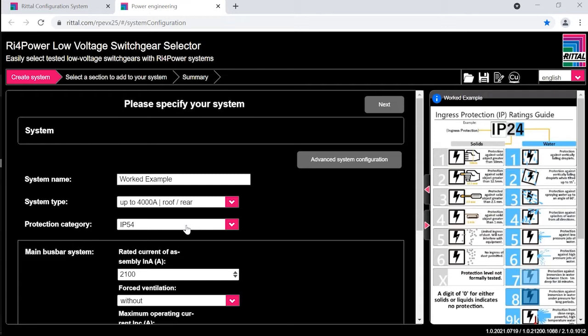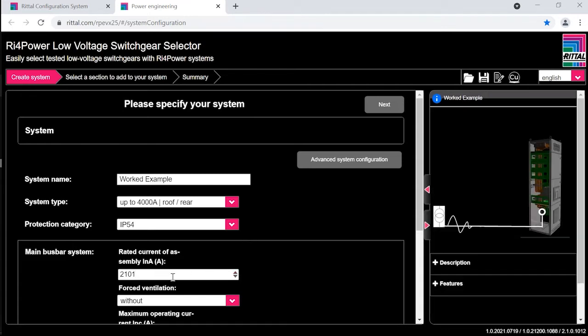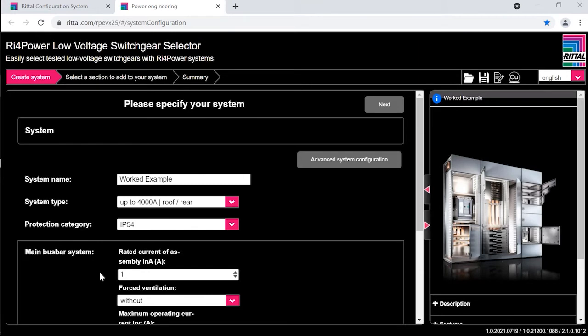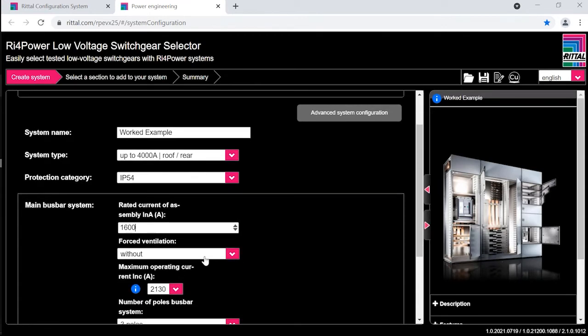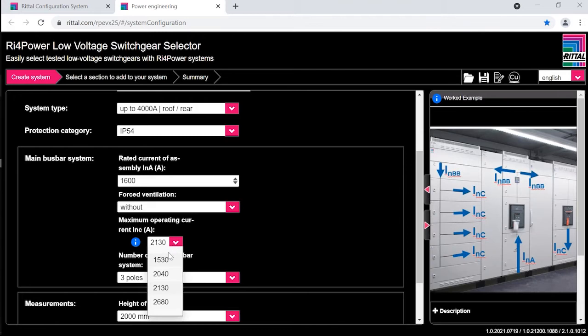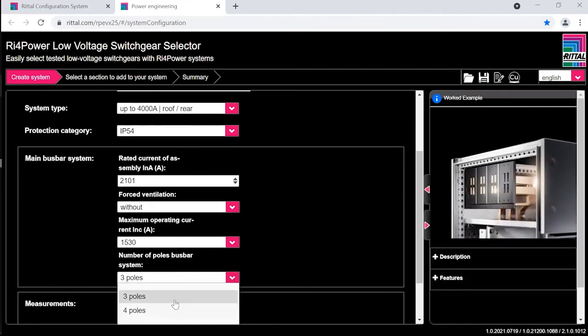We also need to reference our manual on the compartment sizes for the ACB and MCCB circuit breakers. With that in mind, we'll select the rating as 1600 amps for the bus bars. The load current is 1200 amps, which is the design current, but we'll fit in a figure of 1600 amps, a little bit of tolerance there. We don't want any forced ventilation, and the maximum current rating we can achieve is 1530 amps with this particular layout. So that's what I've selected, which is above the 1200 amps loading.